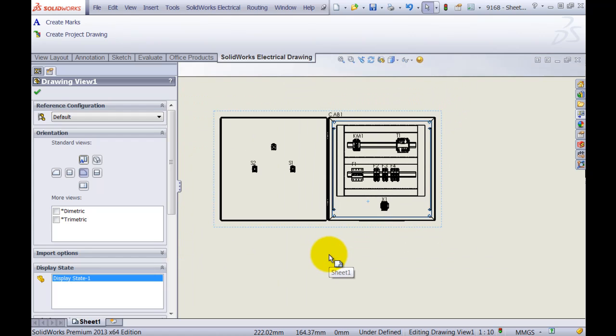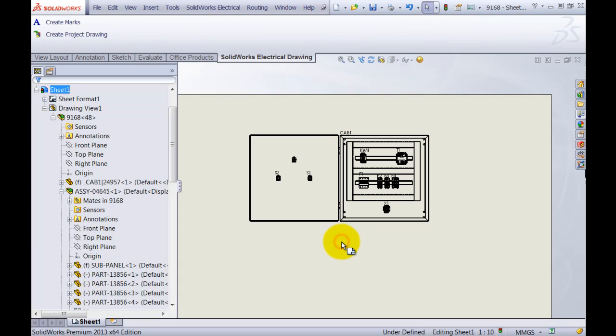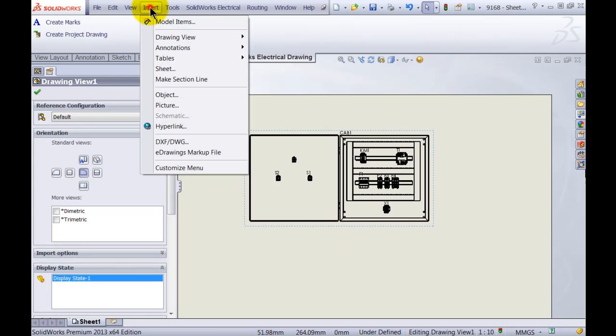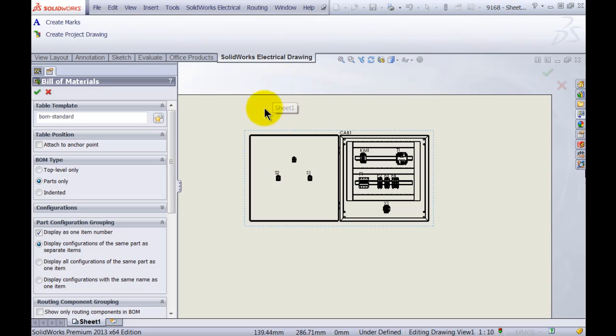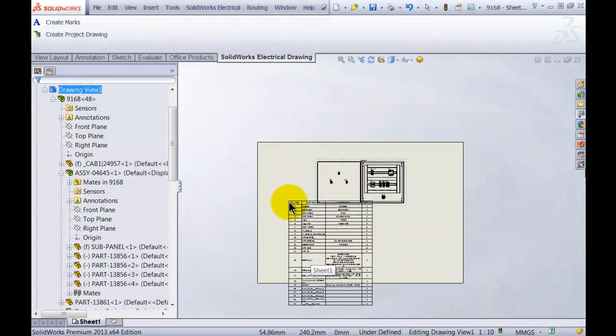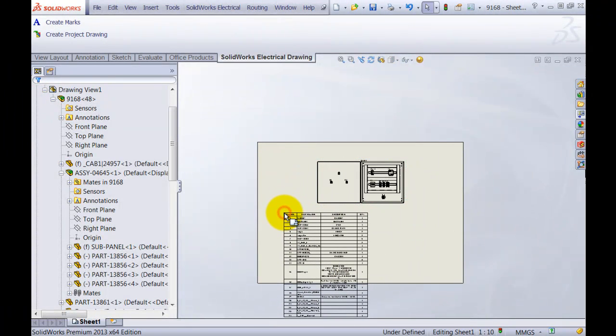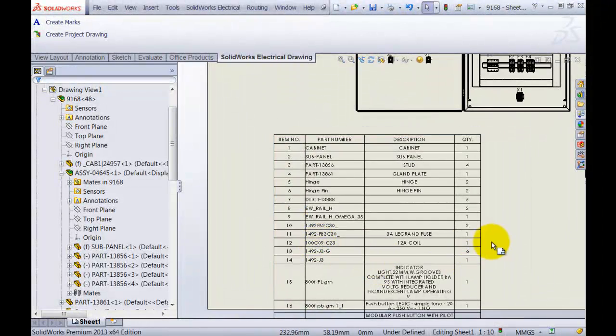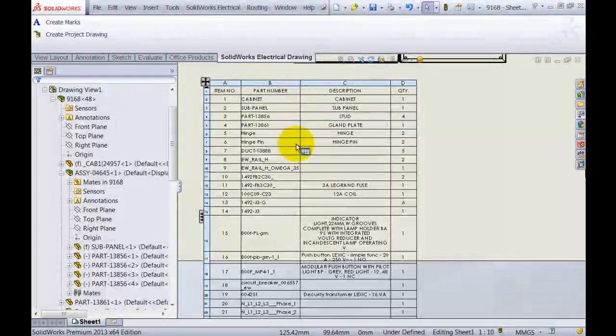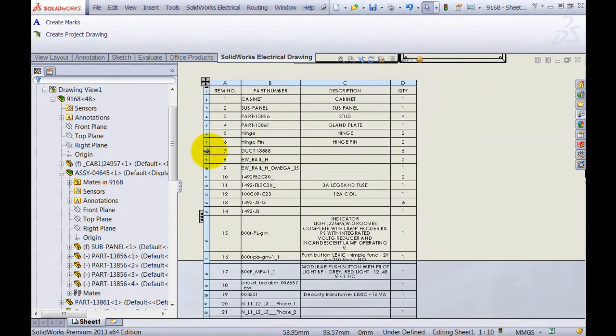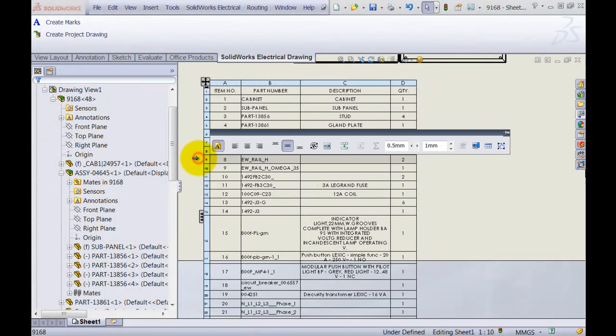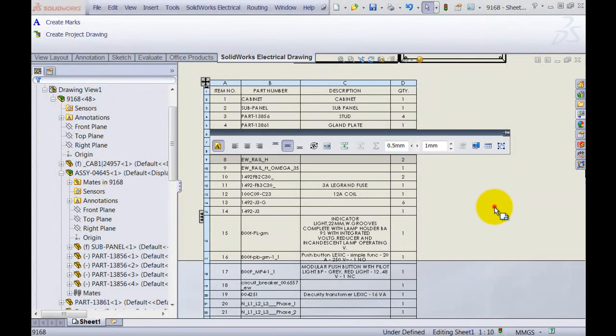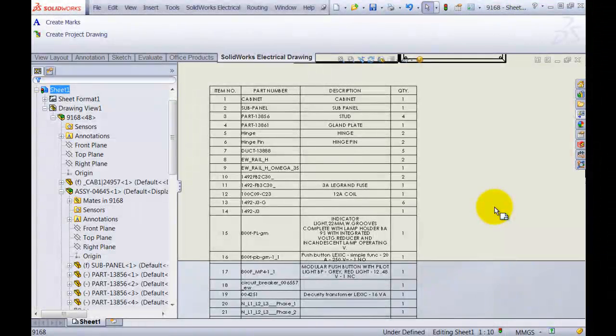Now another thing that we can do is once the 2D view has been placed we can also automatically create balloons and a bill of materials as well. So again preselect view, tables, maybe place a bill of materials. Parts only, I'm happy with that. Maybe just place that on top, like so. Now you can see some components don't have a description assigned to it, for instance my rails and my ducts. The reason why that is is in the manufacturer data manager inside SolidWorks Electrical, it just doesn't have a description applied. So we need to go in there and actually apply the description if we want to.